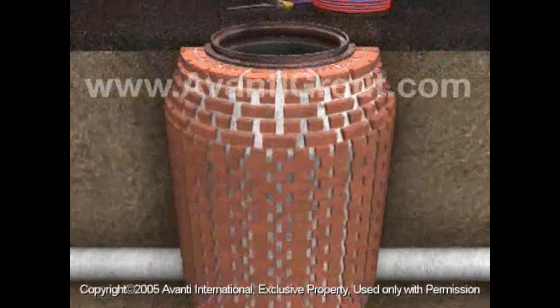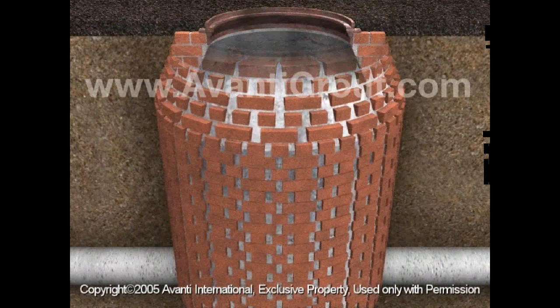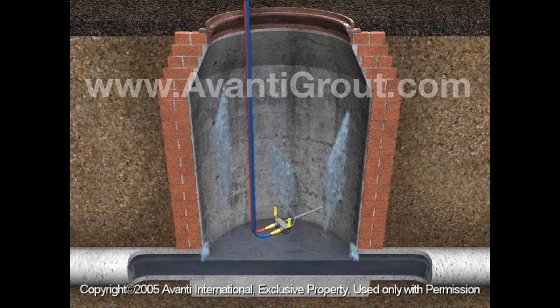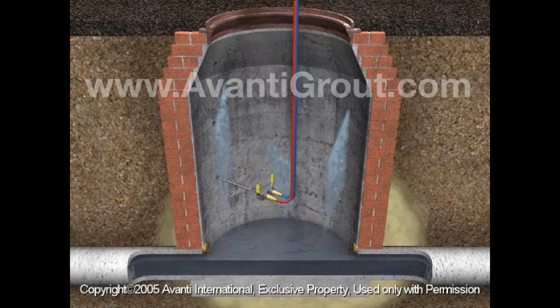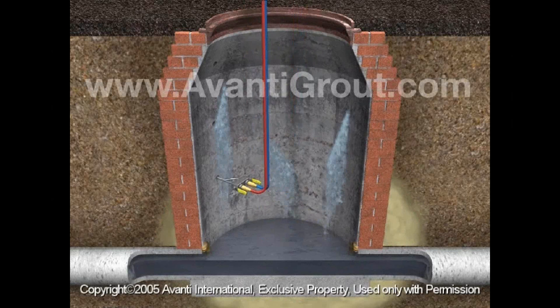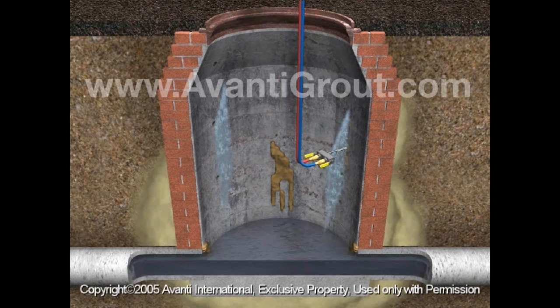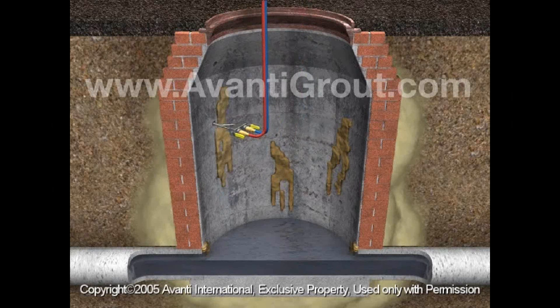Sometimes the manhole has too many leaks to effectively treat each individually. In that case, it can be curtain grouted. In the curtain grouting animation, we use a brick manhole that is leaking. We observe a grout probe injecting grout all the way through the manhole wall out into the surrounding soil. The process is stabilizing the soil and creating a permanent curtain outside the underground structure, proceeding from the lowest point up, with the grout forming a mixture with the soil matrix to stop the water.